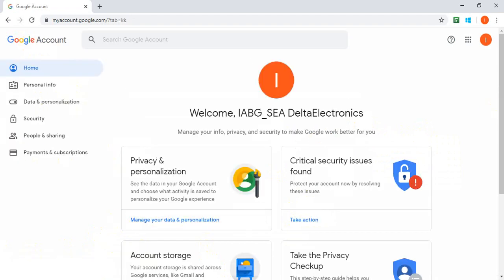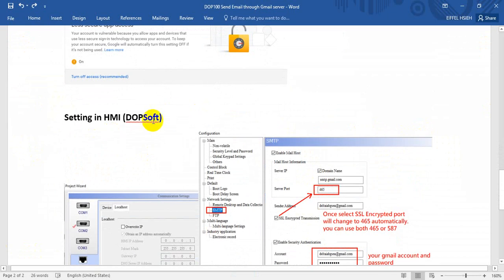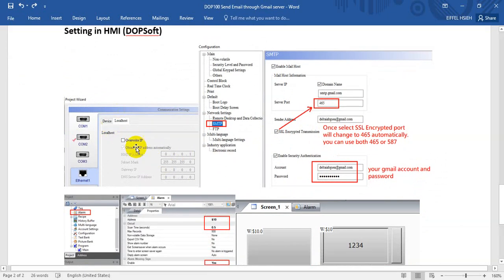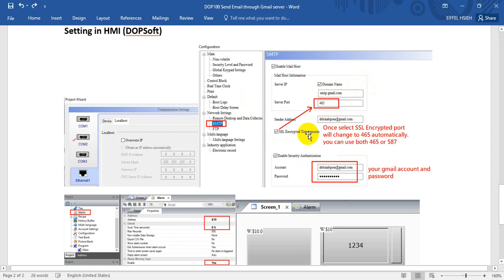Now we do the settings in the DOP software. The HMI will get its IP from the DHCP server. Inside the software we need to configure the SMTP server — enable the mail host and use the domain name for Gmail. Here we enter smtp.gmail.com, and you can select SSL encrypted transmission.